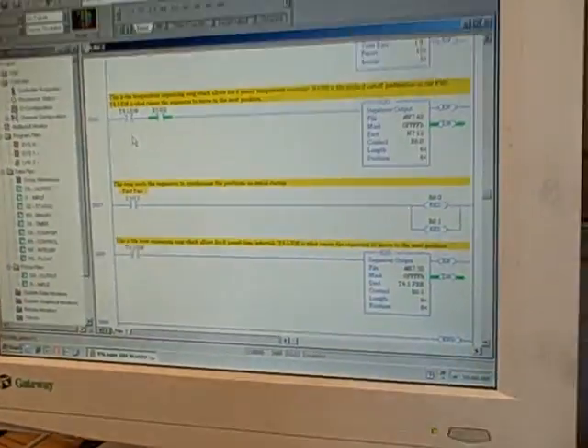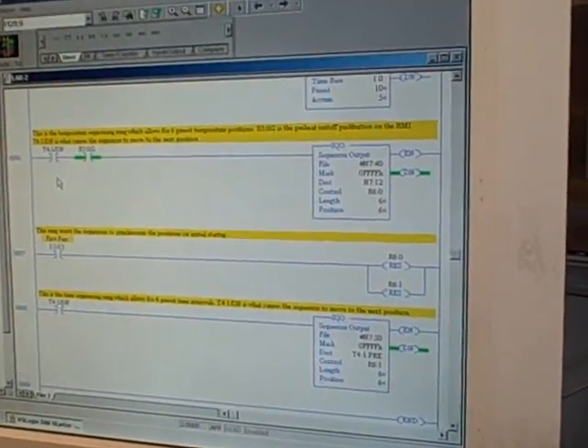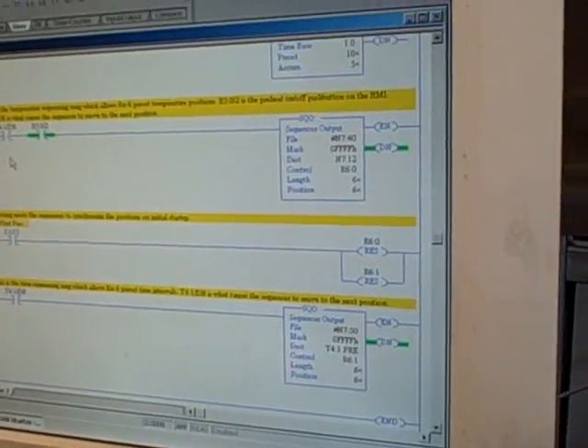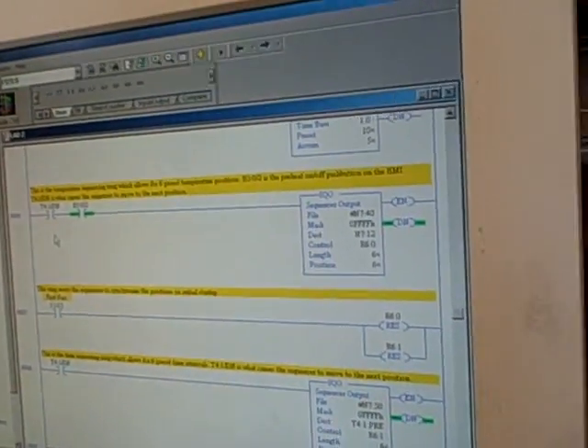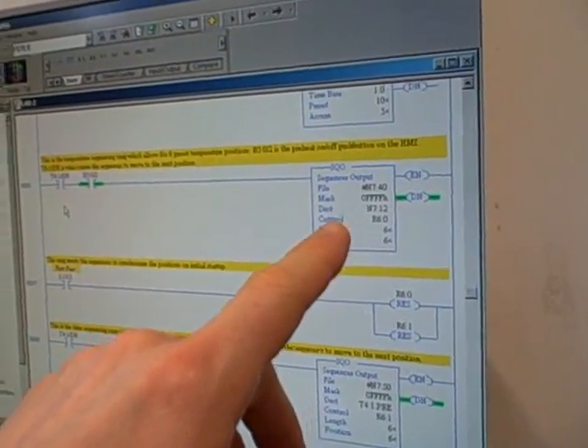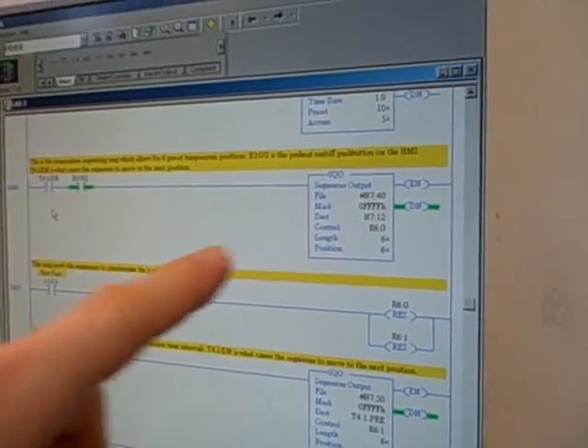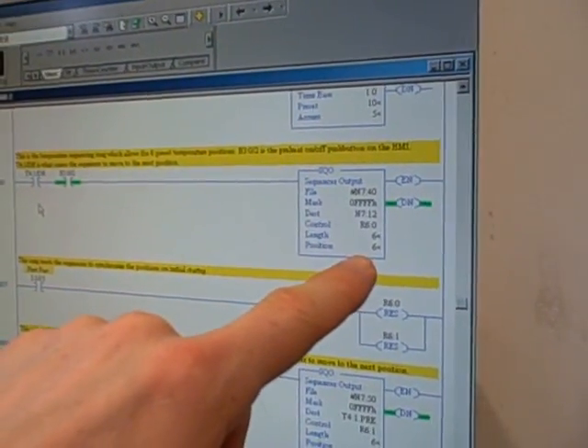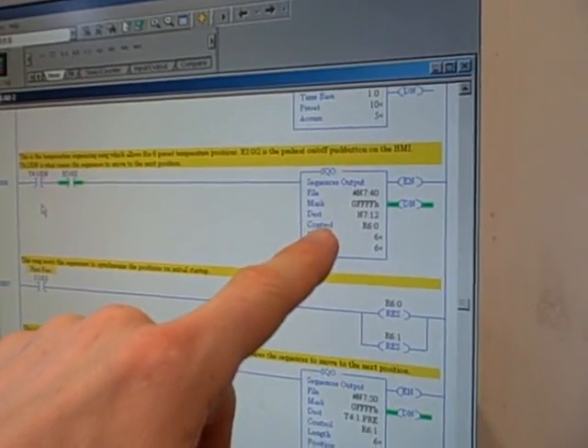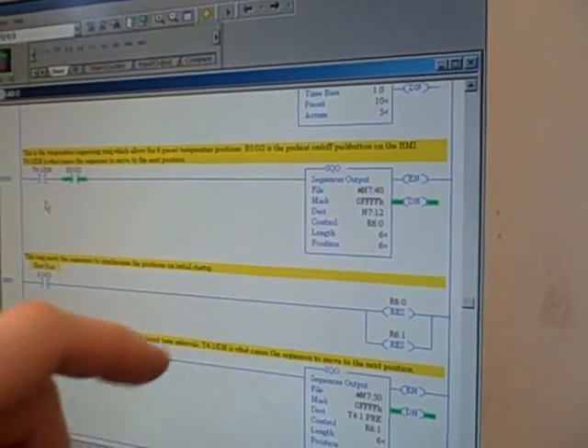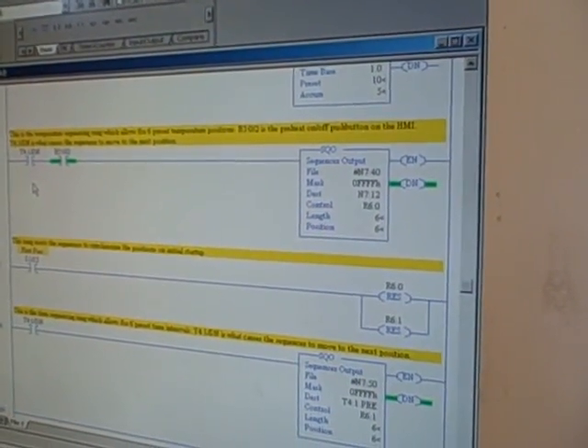The way we do this in the PLC program is we use a couple of SQO instructions in the Allen-Bradley logic. These are the sequencer output. We're using a pair of these. This sequencer right here goes through the six different steps, and what it's doing is calling out of memory these various temperature set points that we put in.